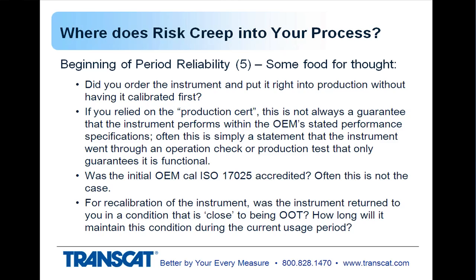And then when you recalibrate the instrument, was it returned to you in a condition that was maybe close to the tolerance limit? How long will it maintain that condition through its next cal interval? So those are some of the things that you need to think about that can cause non-conformance reviews to occur, which cost you money.